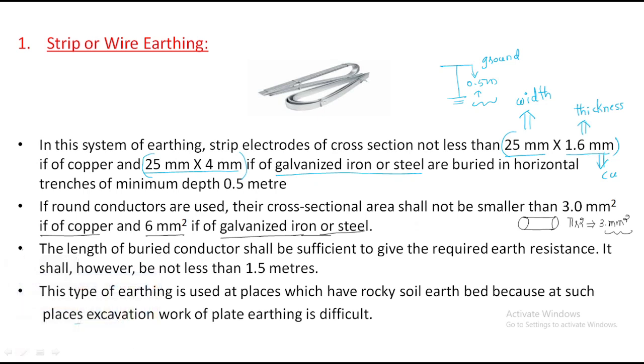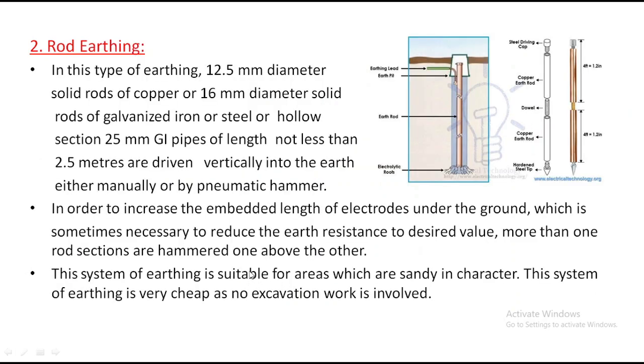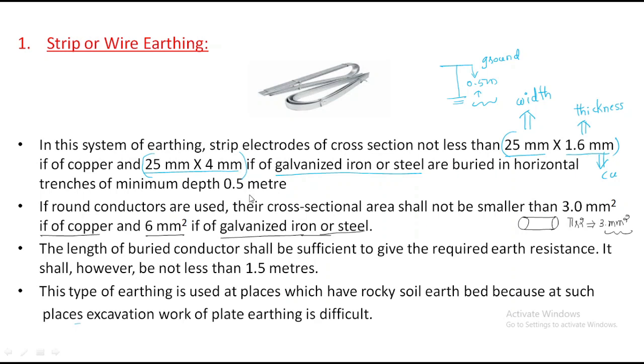Next, the length of the buried conductor shall be sufficient to give the required earth resistance. It shall however be not less than 1.5 meter. So completely it must be 1.5 meters, but 0.5 meters must be buried. Okay? This is 1.5. Generally the complete length from that point to this is 1 meter, and this is 0.5 meter. Complete is 1.5 meter, but in the ground it must be 0.5 meters.